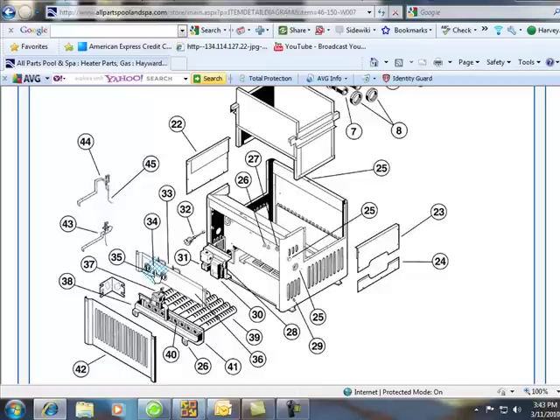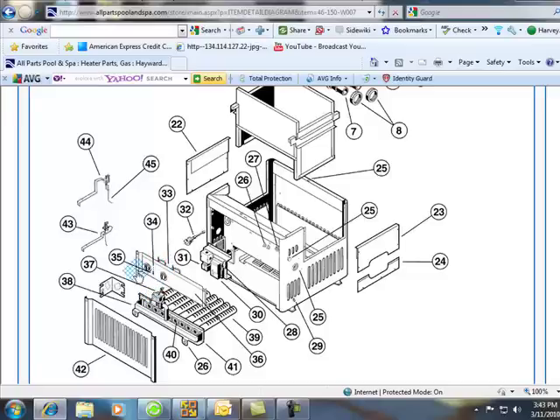If the switch is good, we check from point A to point B, which is the gas valve. And we keep on going through the safety loops.